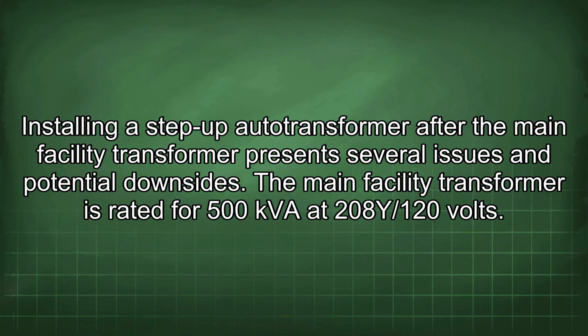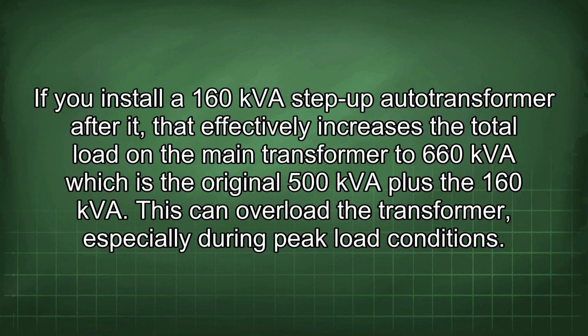Installing a step-up autotransformer after the main facility transformer presents several issues and potential downsides. The main facility transformer is rated for 500 kVA at 208Y/120 volts. If you install a 160 kVA step-up autotransformer after it, that effectively increases the total load in the main transformer to 660 kVA, which is the original 500 kVA plus the 160 kVA. This can overload the transformer, especially during peak load conditions.